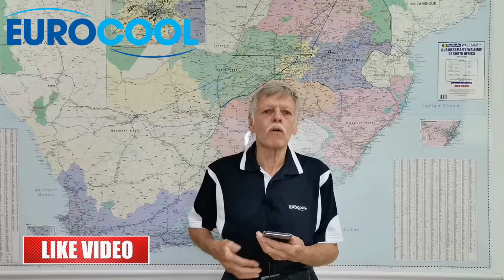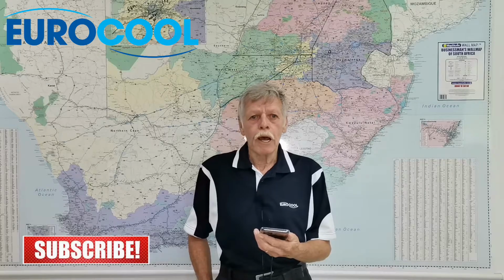When you contact me, give me the error, give me the full unit model number, because there are other error codes in the 2 series that might be slightly different. Although Gree has tried through the years of their manufacture to keep the error codes as uniform as possible. So remember to keep that, and advise your field maintenance guys to always, when they take either a snapshot of the nameplate of the unit, even possibly a snapshot of whatever error code is coming up, because on the smaller units, it cannot store error code history.